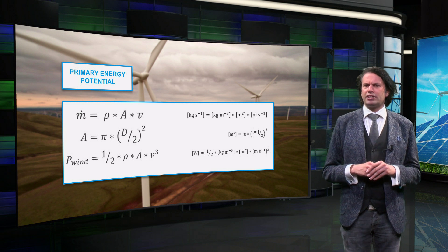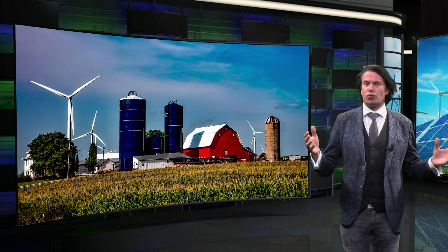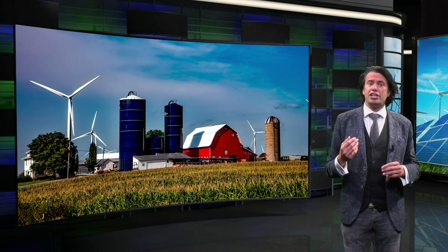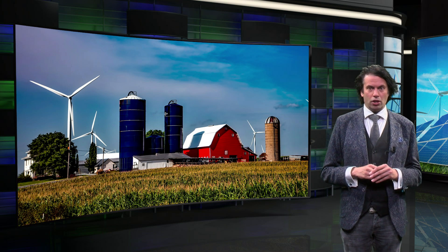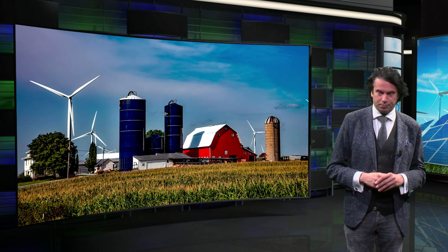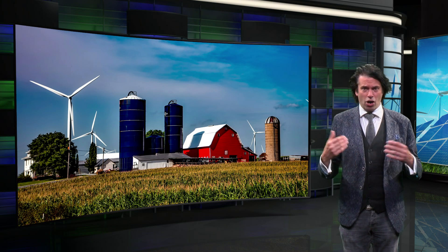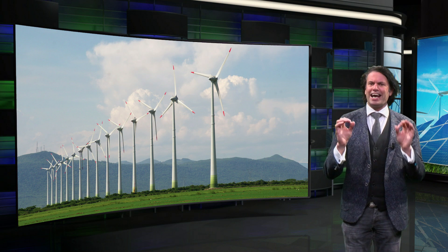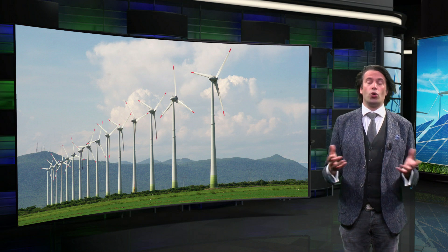This equation shows that the power is highly dependent on the wind speed. As you can imagine, the height and the surroundings of a wind turbine greatly influence the wind speed. High wind speeds are achieved at large hub heights and in close proximity to the coast. An offshore wind park will result in a higher power density in the order of 3 watts per square meters. Any obstacles that interrupt the wind flow, like houses or trees, will lower the wind speed. Also, do not forget that the wind turbines can disrupt each other's air flow. This is very important when you design a wind farm.